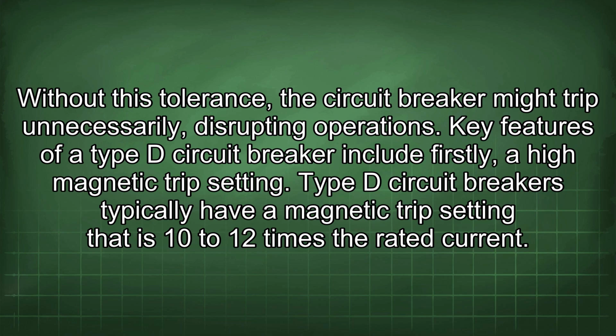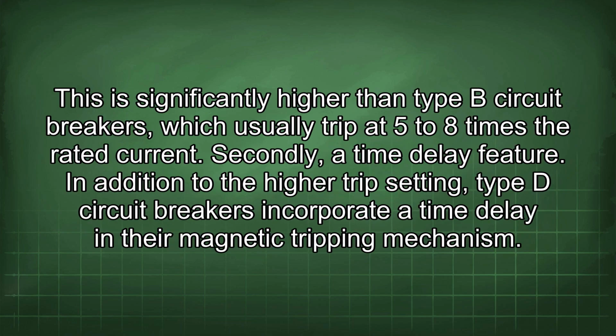Key features of a Type D circuit breaker include, firstly, a high magnetic trip setting. Type D circuit breakers typically have a magnetic trip setting that is 10 to 12 times the rated current. This is significantly higher than Type B circuit breakers, which usually trip at 5 to 8 times the rated current.